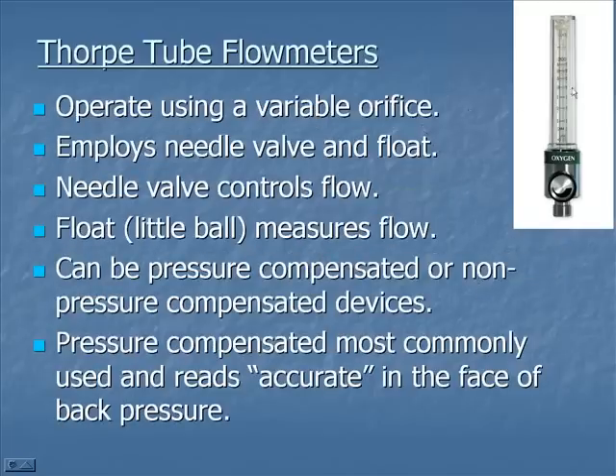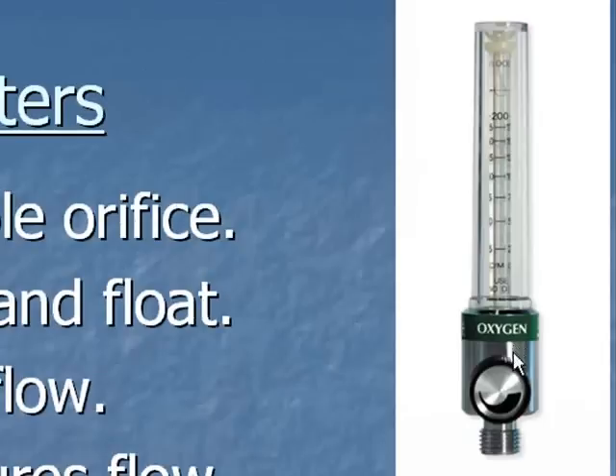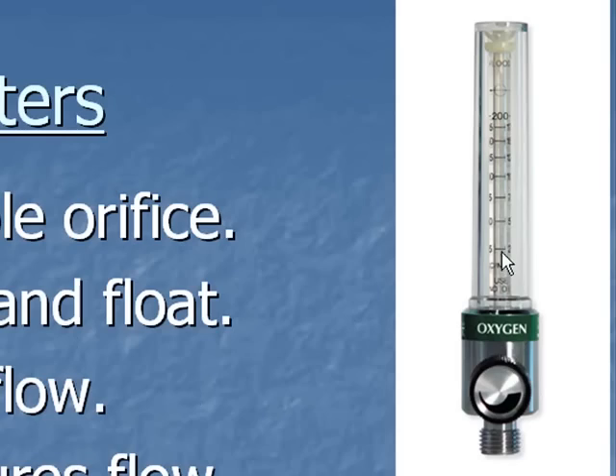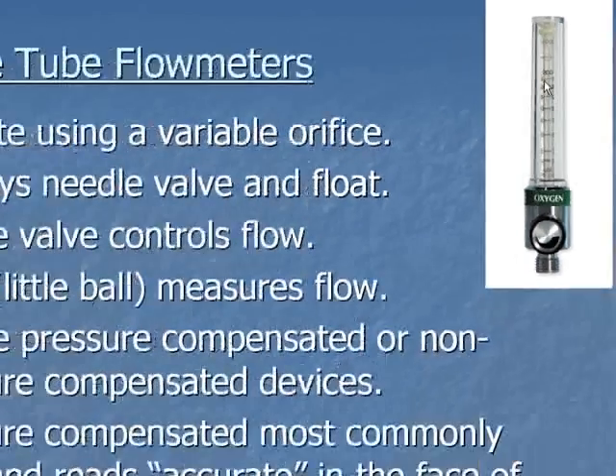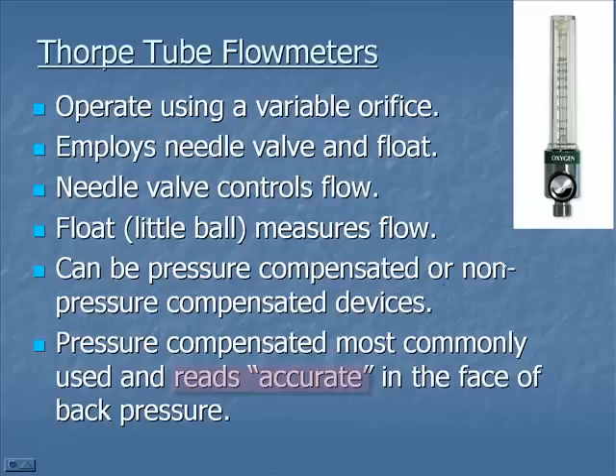The Thorpe tube flow meter is probably one of the most common devices we use. It's typically plugged into the wall at a 50 psi gas source, then reduced so we can regulate the flow. It employs a needle valve and a float — the needle valve controls the flow and the little ball floats up. These can be either pressure compensated or non-pressure compensated, meaning they'll read accurate or inaccurate in the face of back pressure. Most we use today are pressure compensated — they read accurately in the face of back pressure. If you obstruct the tubing, the ball goes to zero, indicating the patient is not getting any flow.